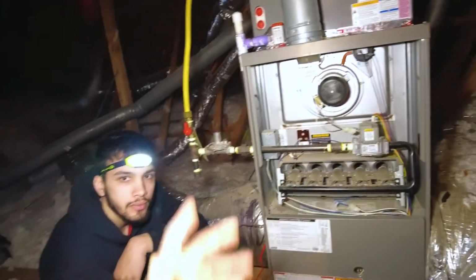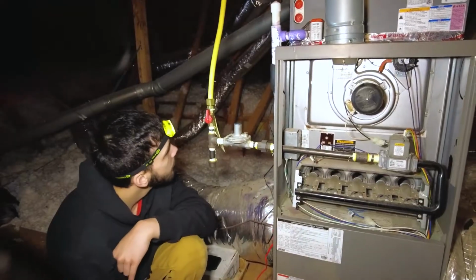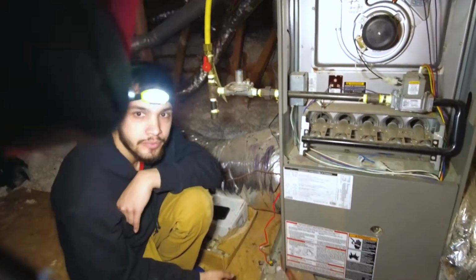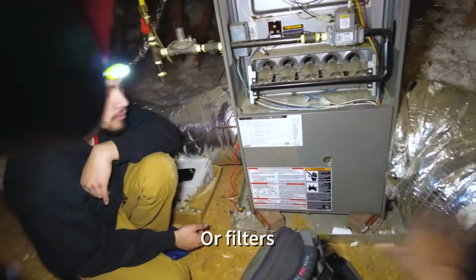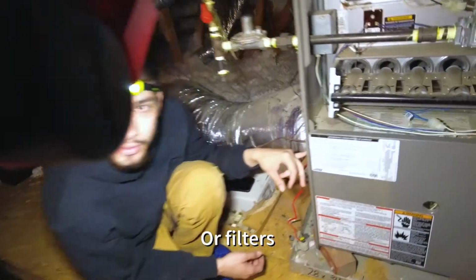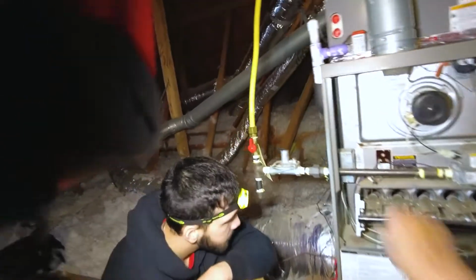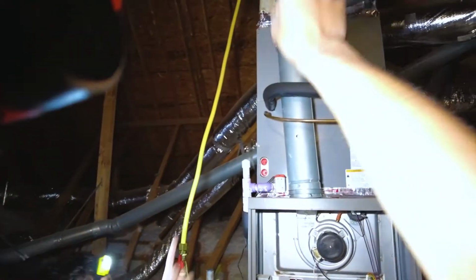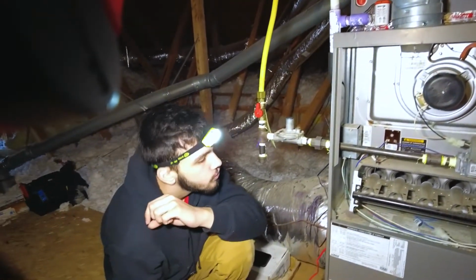And that will cause it to essentially have a high static pressure on this side. The cool thing about it is you'll be able to tell where your issue is. If you have a high number on this side, it's going to be in one of these ducts. Was this our return? Yeah, okay. Absolutely. If you have it on that side, you know it's going to be on the side of the plenum here. So you can kind of assess which one it is.